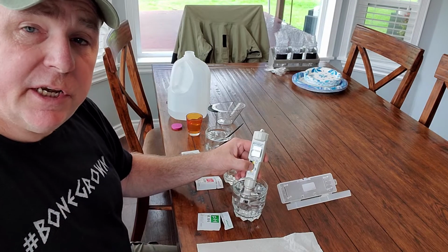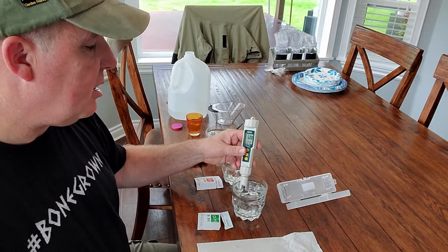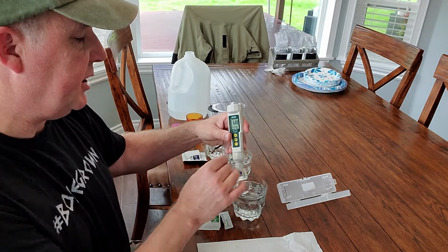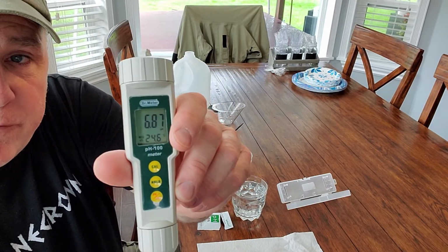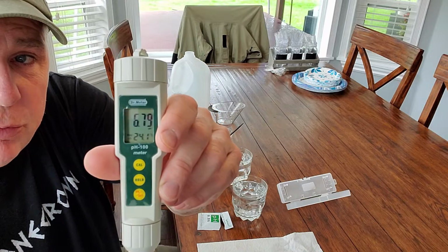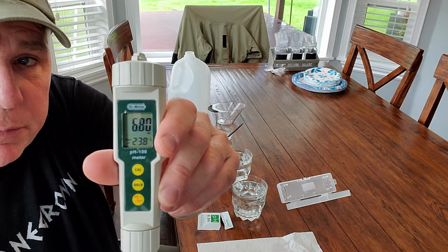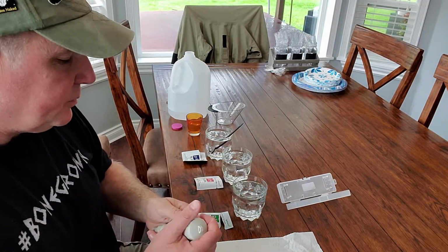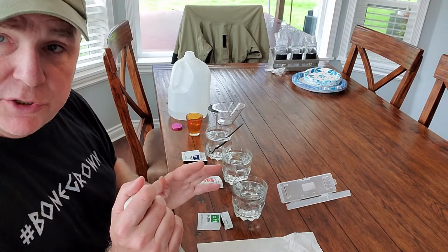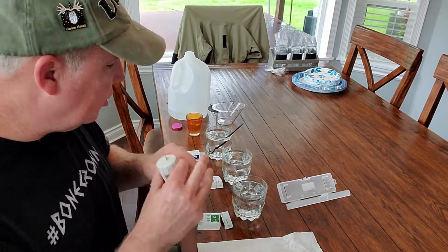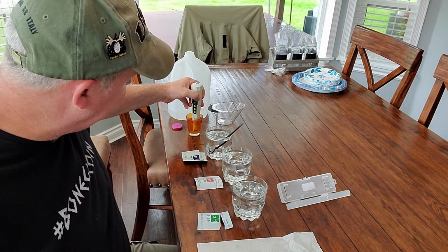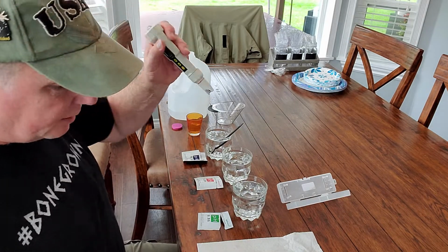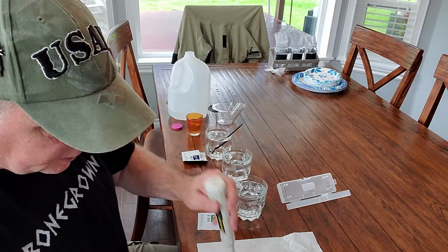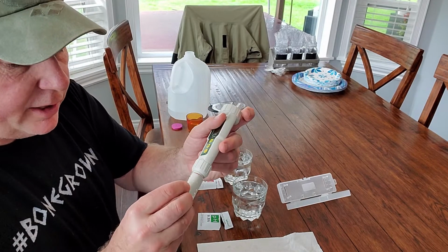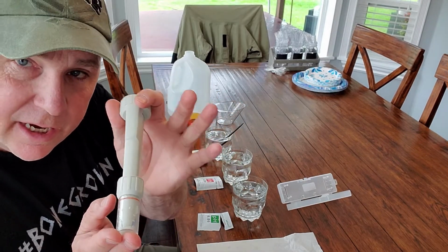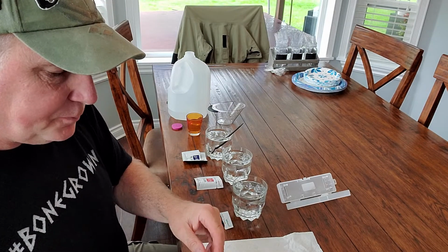Okay, you see here that it went to 6.88, and I'll put a hold on that just so you can see it. And that's at 24.9 degrees, which is what you wanted at its optimal conditions. So I know that my solution is correct. Now I'm going to rinse this meter off with my distilled water, shake it, and then put it away. That's all you need to do, keeping that probe in there damp.